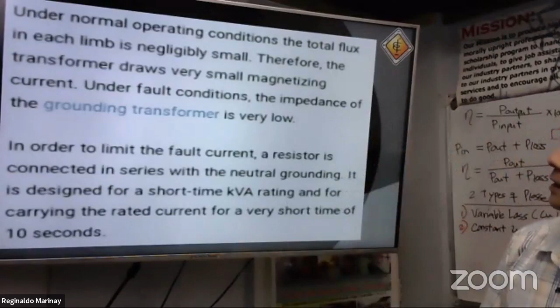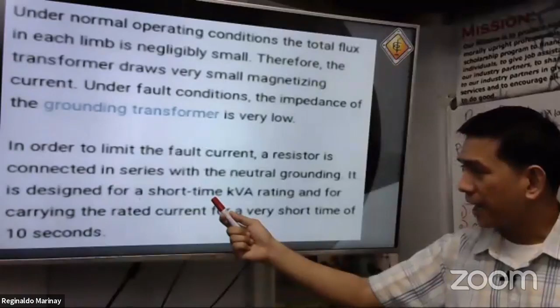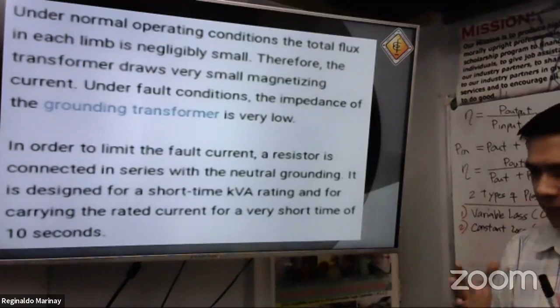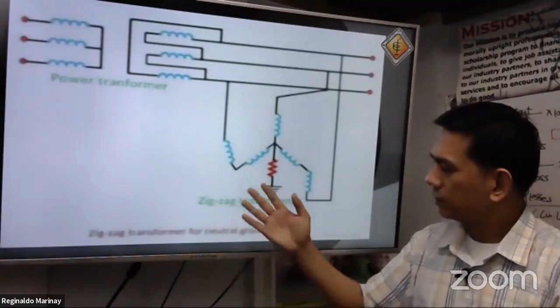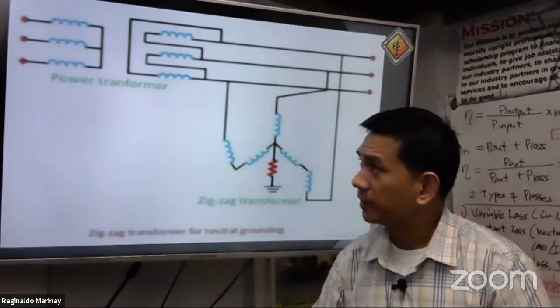In order to limit the fault current, a resistor is connected in series with the neutral grounding. It is designed for a short time kVA rating and for carrying the rated current for a very short time of 10 seconds. Okay? So, ginagamit lang pala to, short time. No? Okay. And for carrying the rated current for a very short time. Okay. 10 seconds lang, no? Yan. Okay? So, therefore, we can say that this also acts as a protection in the system, the zigzag transformer.